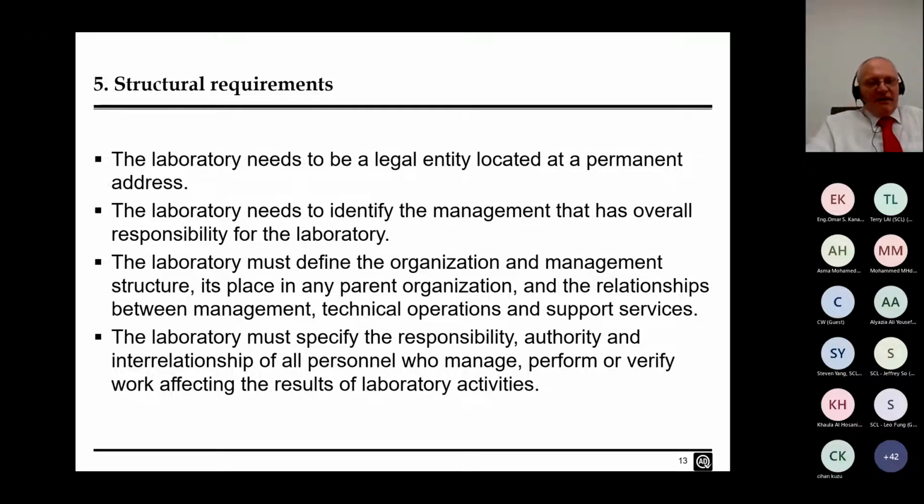So now we get to section 5, and this is where we start to get into the real meat of the standard. The laboratory needs to be a legal entity, and it needs to be located at a permanent address. It needs to be something that can be found and something that can be sued ultimately, because your certificates are legal documents. If there's any issues with them, somebody may want to make a legal case.